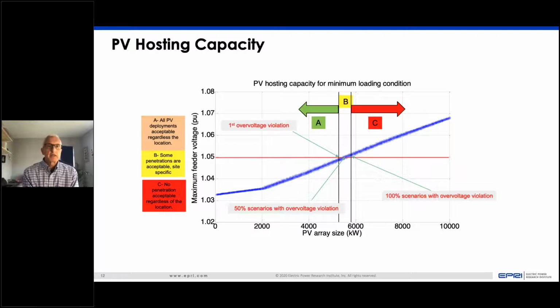This is an example of a chart like that, where the hosting capacity limiting factor might be voltage. As we get more and more PV on a distribution system, and it's generating energy during the day, it can result in a voltage rise on the distribution system as that current flows from the PV inverters—the PV generation—back towards the substation.